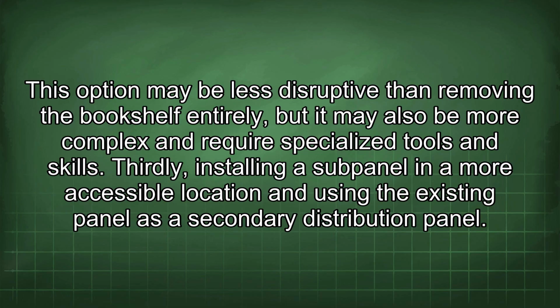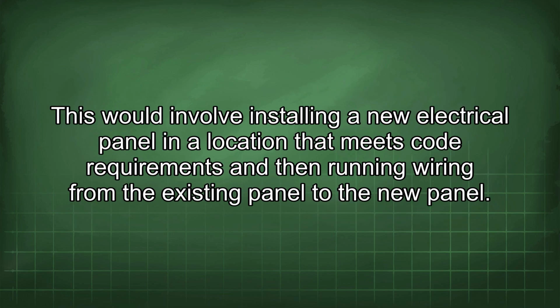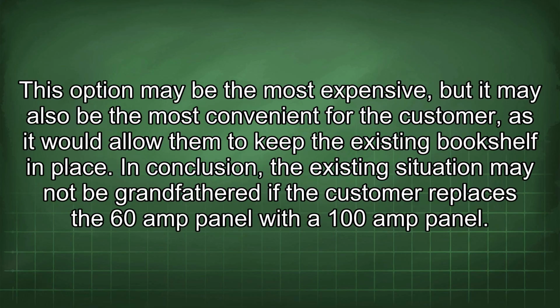Thirdly, installing a subpanel in a more accessible location and using the existing panel as a secondary distribution panel. This would involve installing a new electrical panel in a location that meets code requirements and then running wiring from the existing panel to the new panel. This option may be the most expensive, but it may also be the most convenient for the customer, as it would allow them to keep the existing bookshelf in place.